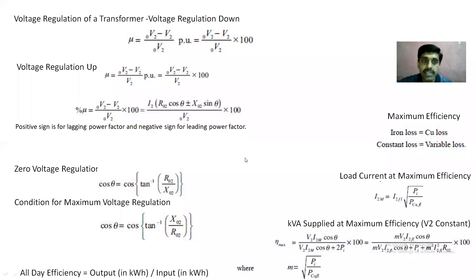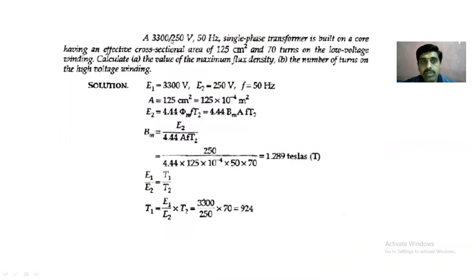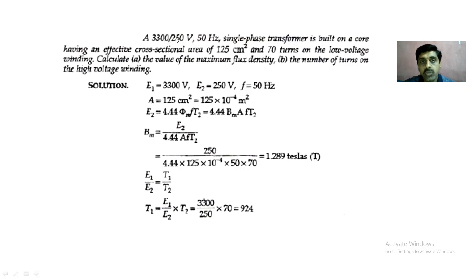We will now see problems on single-phase transformers, and also some problems on three-phase transformers. Let us have some more problems based on the theory discussed. The first problem: a 3300/250 V, 50 Hz transformer is built on a core having an effective cross-sectional area of 125 cm². There are 70 turns given on the low-voltage winding, that is the 250 V side. Calculate the value of the maximum flux density and the number of turns on the high-voltage winding.